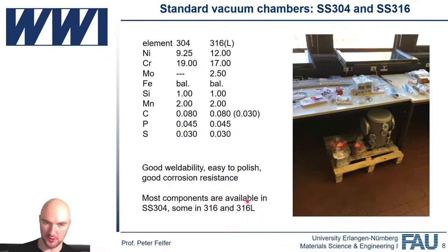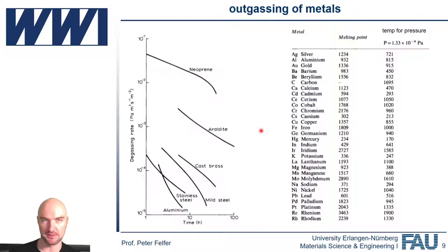But if you do electropolishing, you usually go for these because they don't tend to form pitting on the stainless steel chamber, which usually is a trap for dirt, and we don't like dirt in our systems.